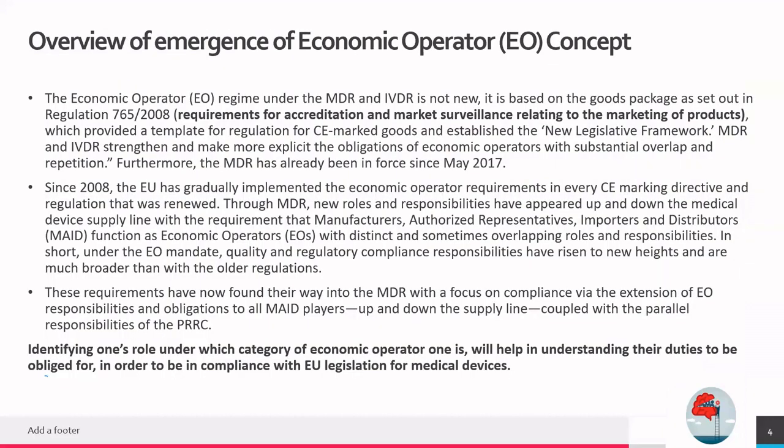So let's discuss the concept, the birth of the economic operator, right? The economic operator regime under the MDR and IVDR is not new. It is based on the goods package as set out in regulation 765/2008, which is nothing but requirements for accreditation and market surveillance relating to the marketing of products.